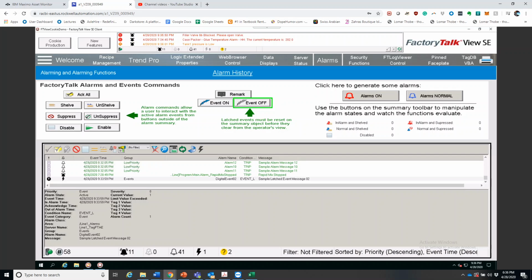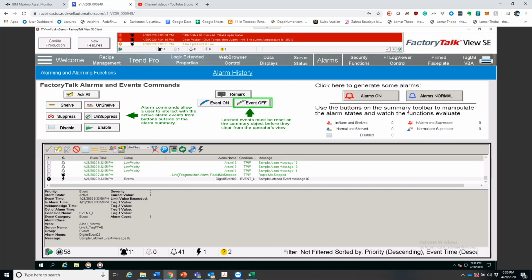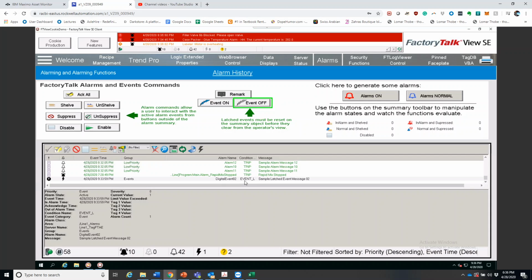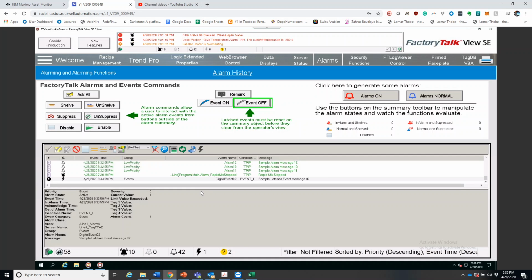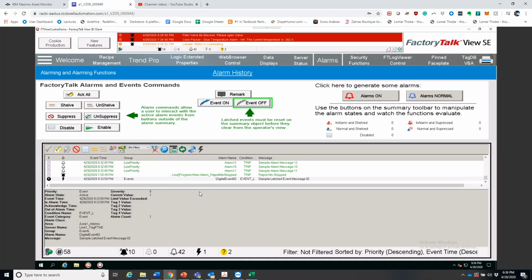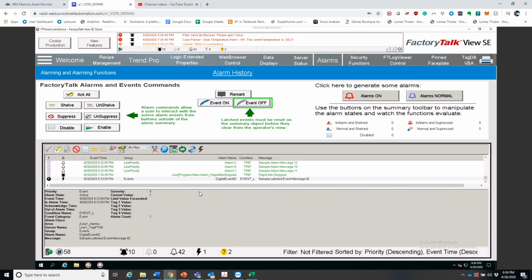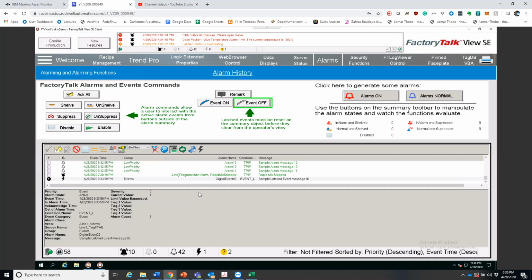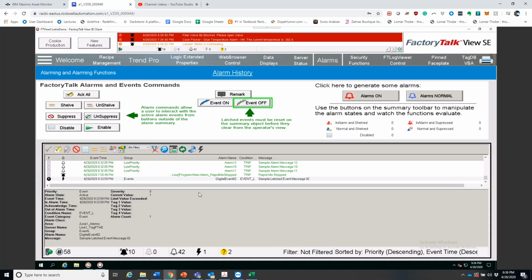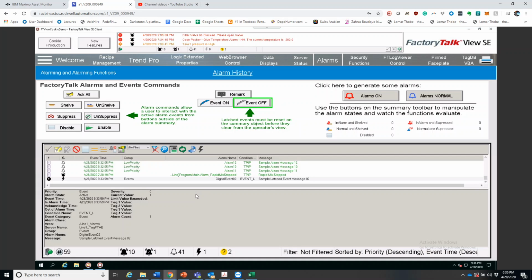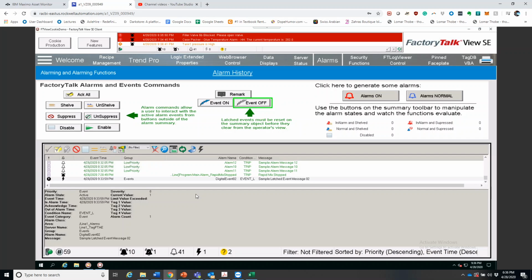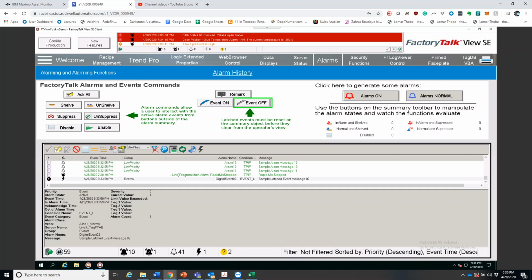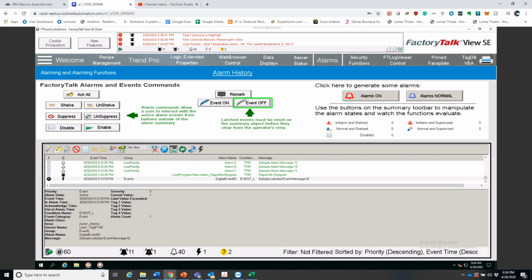However, only one event will disappear from the alarm summary. The digital event 02 will remain on the list, which it does. The reason for that is the latch nature of this event, which means that the event remains active even when its condition has returned to normal. To allow a latch alarm to return to normal after its condition returned to normal, the operator must reset the event.